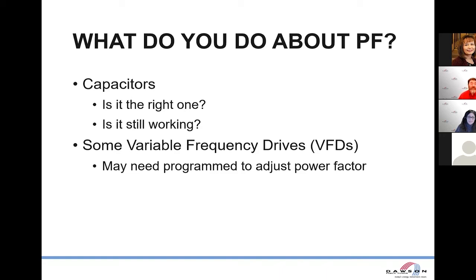Now let's say you've got a variable frequency drive. Those don't need capacitors. Why am I below 90% if I have a variable frequency drive? Well, the most likely culprit is that it's not programmed correctly to fix the power factor. You're going to want to call the manufacturer of the variable frequency drive, or the installer, to get that corrected.